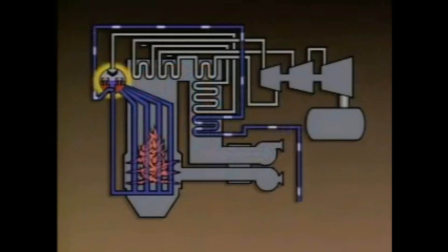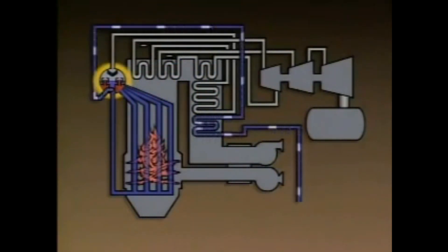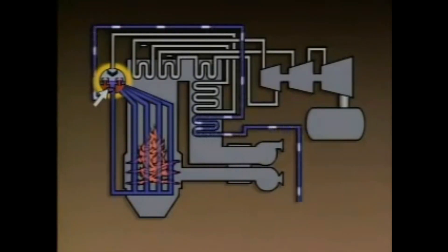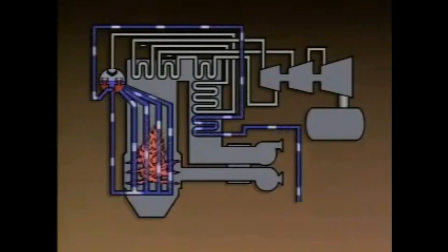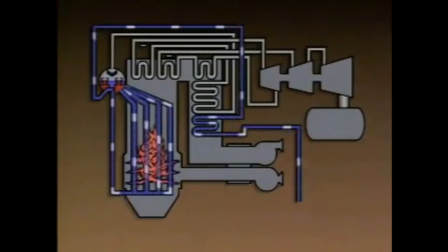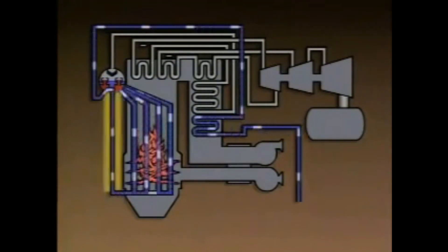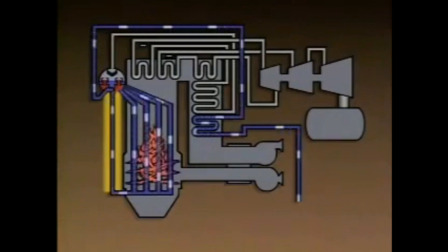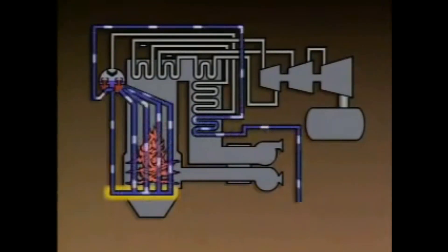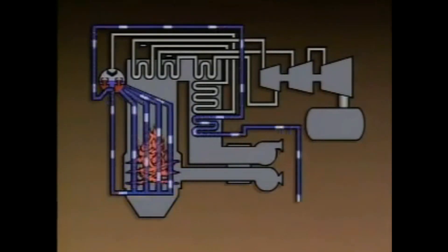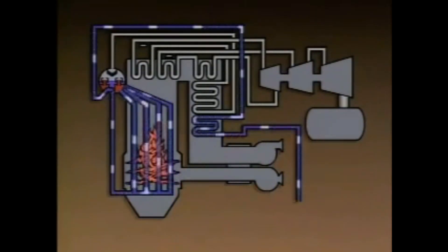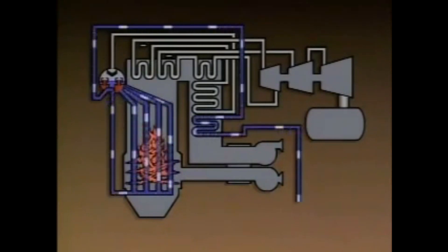In this boiler, the heated feed water flows from the economizer and enters the bottom part of the boiler drum through the feed water inlet. The water continually circulates within the boiler through the downcomers, the lower headers, and the boiler tubes. A boiler typically has two or more downcomers and two or more headers. However, for clarity, this illustration shows only one of each.